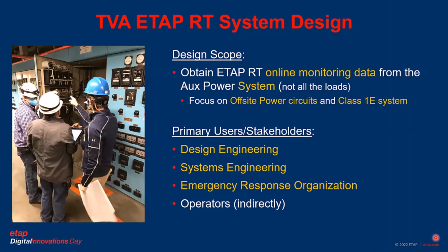Now let's look at the specific TVA ETAP RT system design concepts. First of all, our design scope is to obtain online monitoring data from the auxiliary power system, and it's the system we're after, not all the loads. We would have to put way too many sensors in to be able to gather data on every load in the plant, but just knowing how the system behaves is the goal. And we're going to focus on two things: offsite power circuits and Class 1E systems. And in my industry, those are the critical electrical systems that are important to nuclear safety.